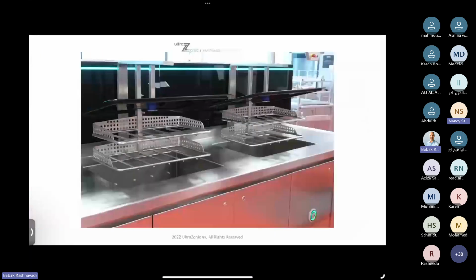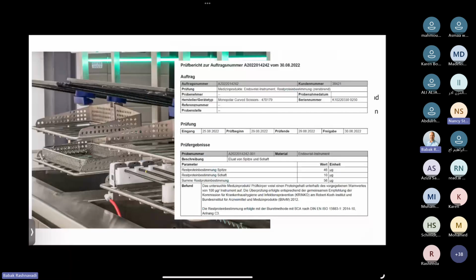This was a report, no problem. The report just showed the Da Vinci instrument. Unfortunately, I had to do that. I promised Babak that I would translate it into English, but on the bottom you see the residual protein determination, this 10 micrograms. This is the cleaning efficacy inside the instrument. So we have only 10 micrograms, which is nearly nothing of protein residue in the instrument. This is unbelievably good. Even Da Vinci came to us and said, wow, Nancy, we never had such a device that could achieve that kind of goal. Next, please.